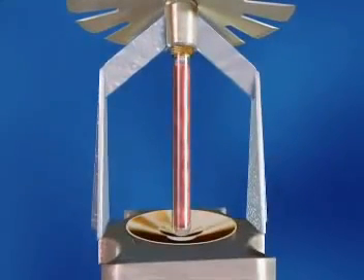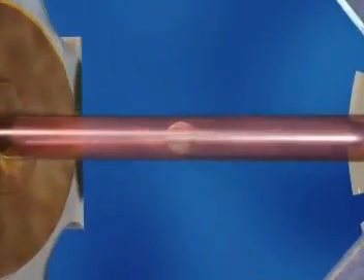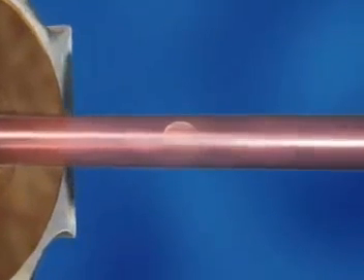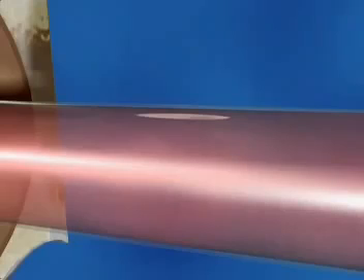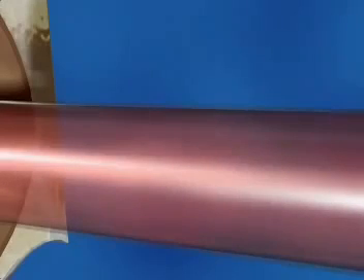A small measured quantity of vapor remains trapped when the bulb is hermetically sealed. When the liquid expands under the influence of heat from a fire, pressure in the bulb rises until the vapor is compressed.